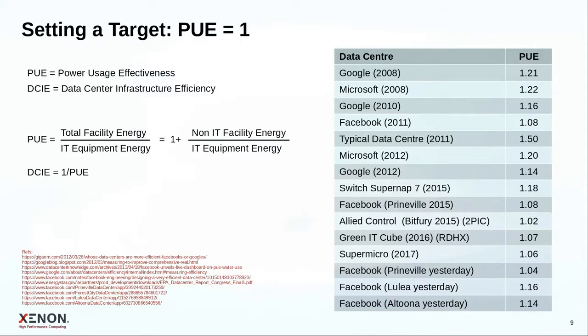That's pretty interesting when we look back at some of the first large data centers where we have numbers available from Google and Microsoft, for example. In 2008 they were very happy to have a PUE of 1.2, which at that time meant that for 20% of the power used to run the IT, they had to add another 20% just to keep the cooling going. Google and Microsoft were really proud of those numbers, saying 'we have the greenest data centers on the planet, look at us, how cool we are.' Let's have a look at where we are typically - from the US government, there are numbers for typical data centers around 2011, which were at about 1.5. That's still not bad considering some really badly designed centers were running at about 2 or 3, with large overheads in power consumption.